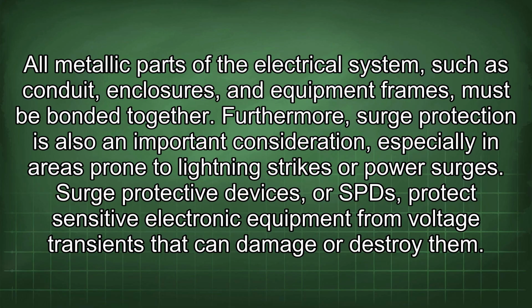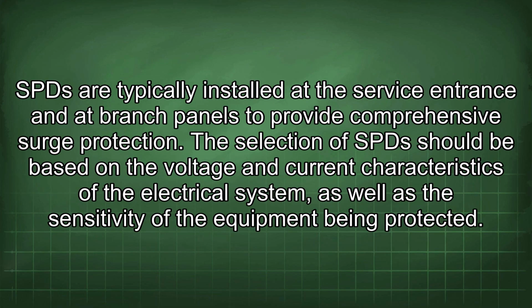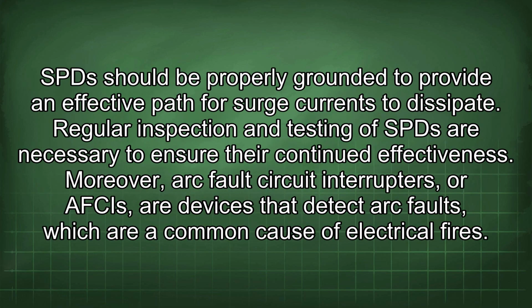Furthermore, surge protection is also an important consideration, especially in areas prone to lightning strikes or power surges. Surge protective devices, or SPDs, protect sensitive electronic equipment from voltage transients that can damage or destroy them. SPDs are typically installed at the service entrance and at branch panels to provide comprehensive surge protection. The selection of SPDs should be based on the voltage and current characteristics of the electrical system, as well as the sensitivity of the equipment being protected. SPDs should be properly grounded to provide an effective path for surge currents to dissipate. Regular inspection and testing of SPDs are necessary to ensure their continued effectiveness.